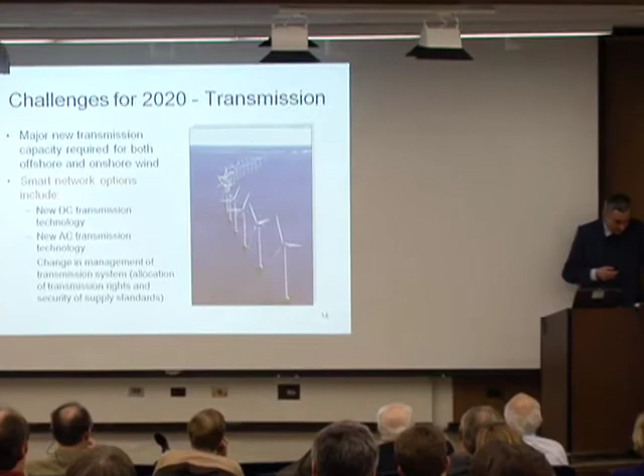In terms of transmission, major new transmission routes are required, both onshore and offshore in this example. There are interesting technical innovations, such as high voltage DC, particularly voltage source HVDC, now available up to about 1,000 megawatts capacity at plus or minus 300,000 volts. There are also interesting ideas for improving the transfer capacity of AC lines, which have been around for about 20 years.